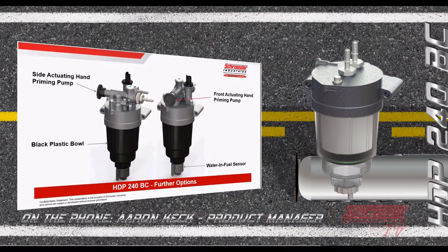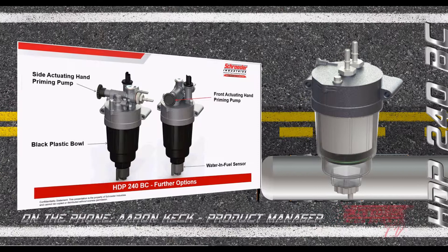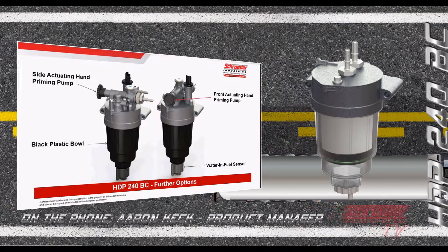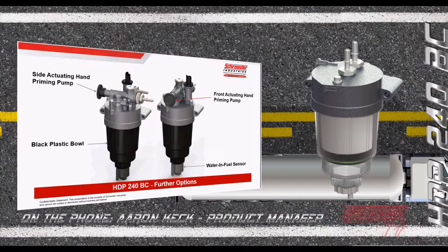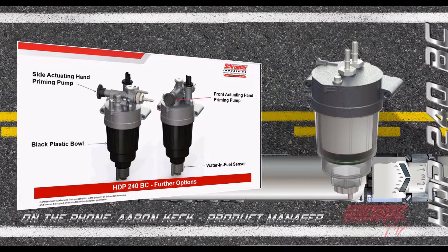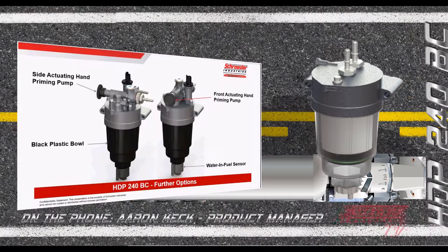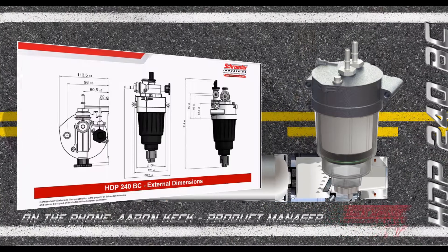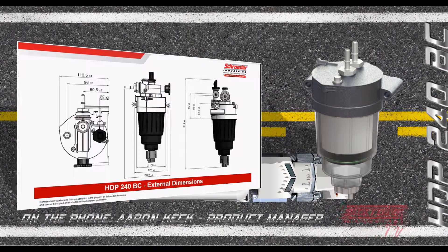If a clear filter bowl isn't preferred, a black plastic bowl is also offered. Because it's opaque, we incorporate a water-in-fuel sensor at the bottom with a drain to monitor water level within the bowl. The modular hand priming pump can be reoriented front to back rather than left to right, and the heater port can be rotated for flexible porting — left to right, front to back, side to side, or top to bottom — giving great flexibility in plumbing. The overall dimensions shown represent the maximum design envelope for the HDP 240.